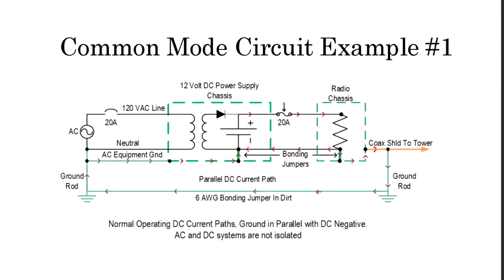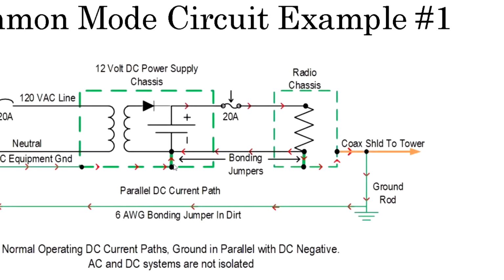Okay, let's go back to where we were a few pages ago, back to our DC power supply, before we pulled the jumper out of this DC power supply, and also compounded by the jumper in our radio equipment. We are forcing common mode current in this application. It's DC. It doesn't necessarily cause us any real noise problems, but it does cause us some corrosion problems. But the main reason is because we've bonded a neutral conductor, our reference conductor, to ground. We've done it more than one place.